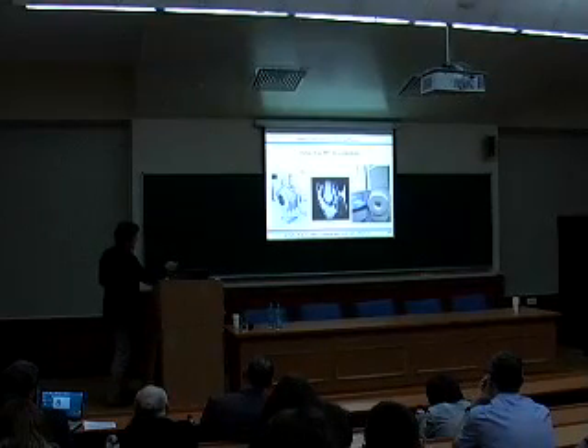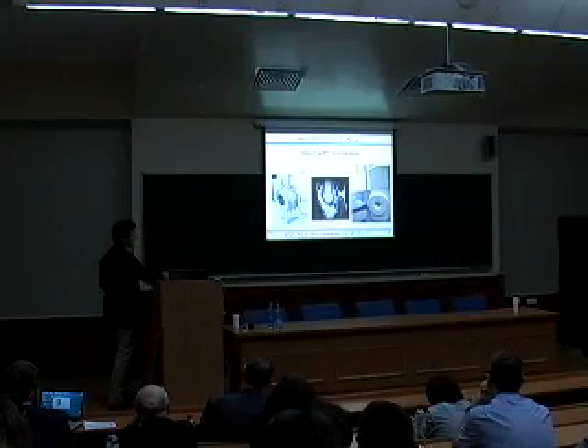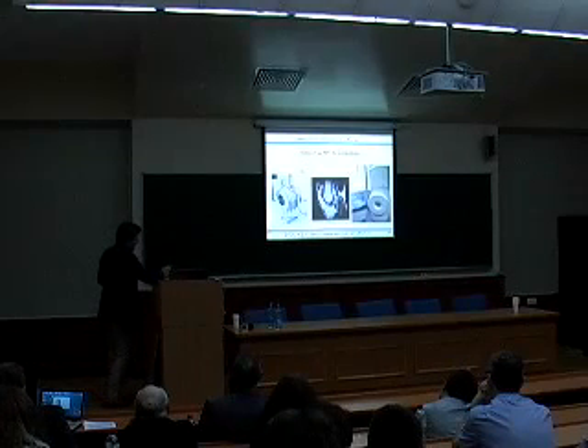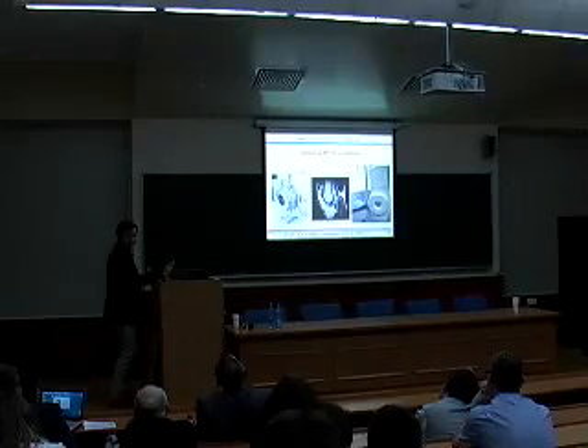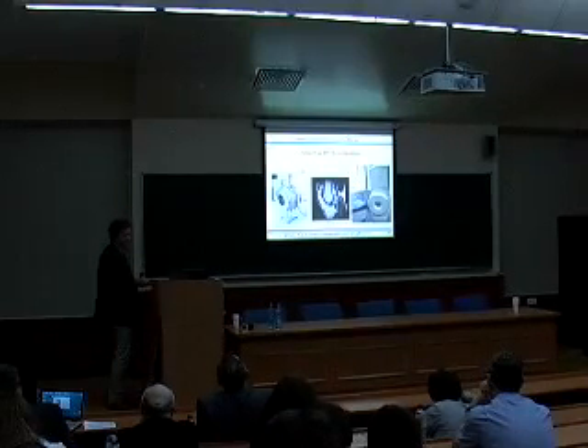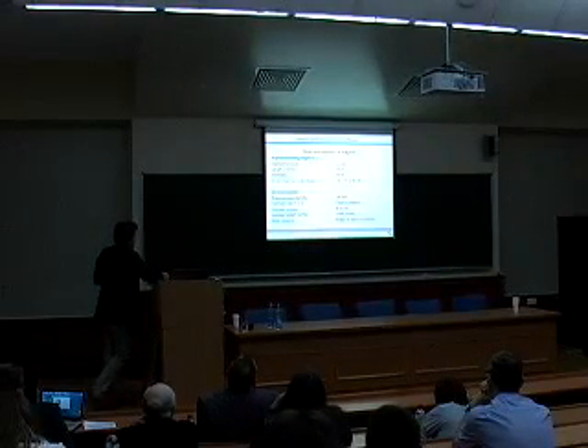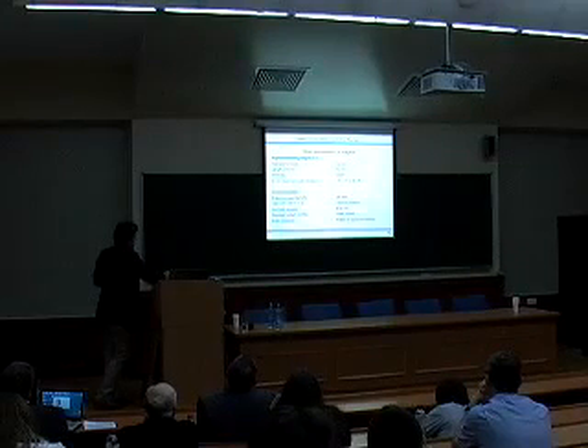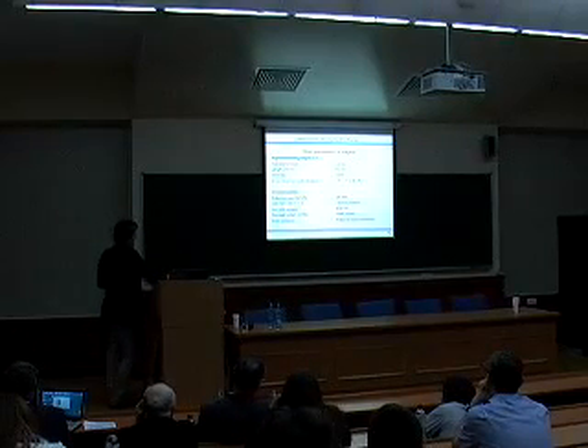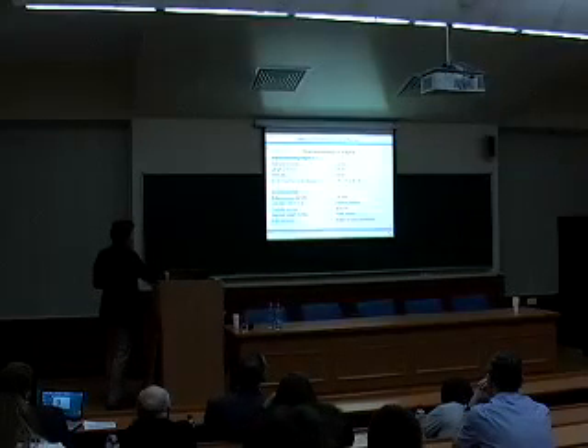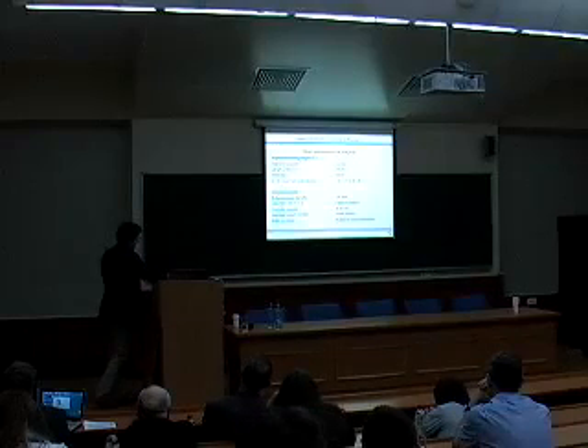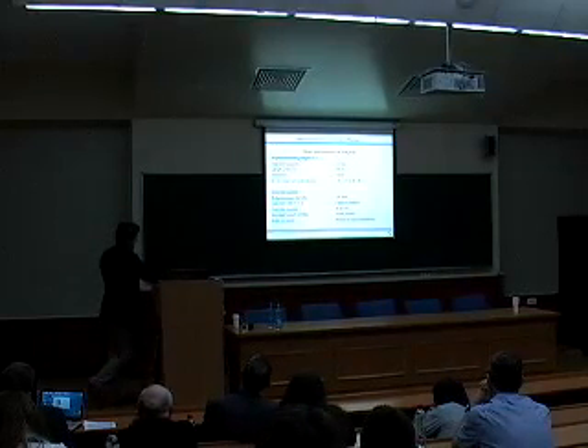So we tested it for half a year, at least, and it's working safely. And important is that the field value is also very stable. It's very important for doctors. In the other case, you see nothing. But here are the parameters. Here's the diameter model for this model. Length of tunnel is 600 millimeters. Shielding is active. Zero field is at this distance from center. Patient access diameter is 220, gradient coils are passive shielded, and gradient strength is 30 millitesla per meter. The gradient system is water cooled.